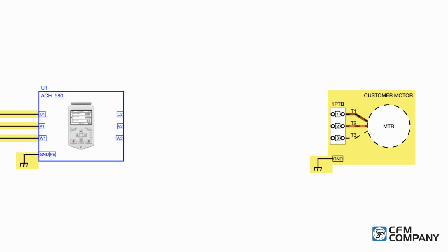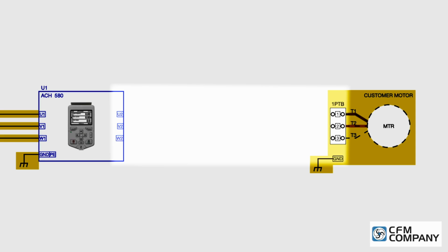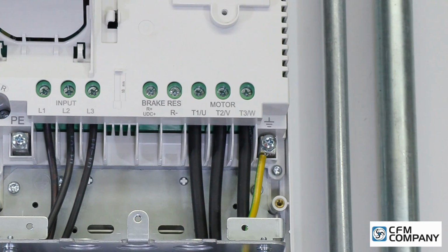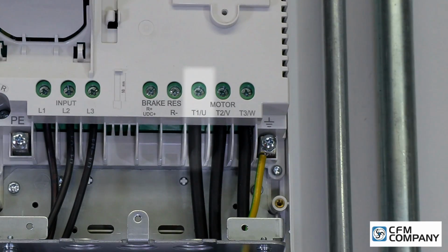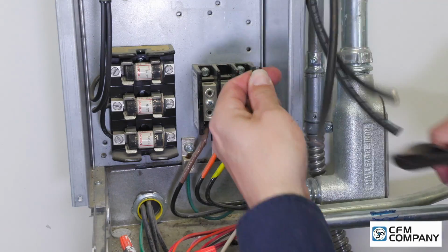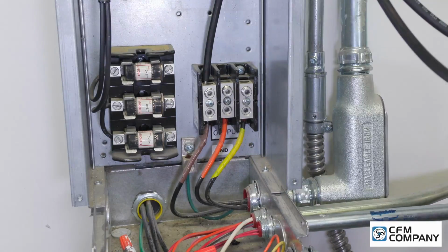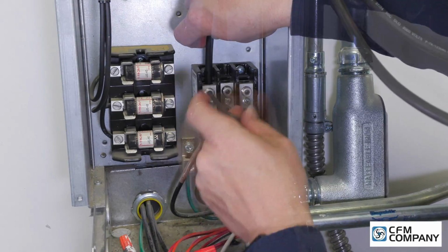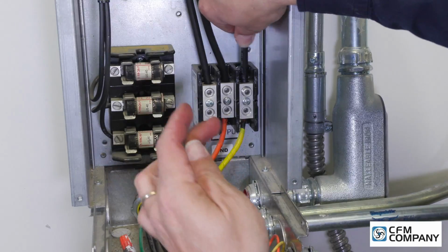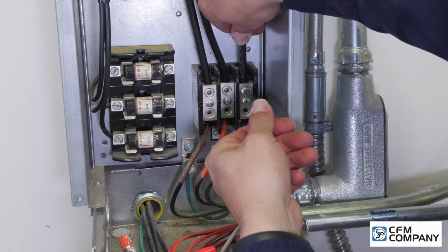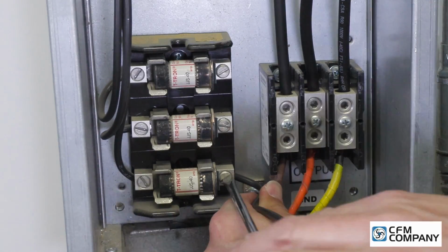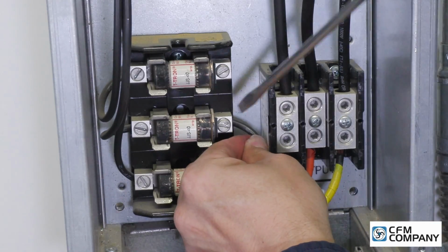The new conductors will need to reach between the drive output terminals and the motor terminal block. Land each new conductor on the drive motor terminals T1U, T2V, and T3W. Land the original ground conductor to the drive ground terminal. Cut the new output conductors to length at the motor terminal block. Land each output conductor to the line side of the motor terminal block. Next, install the 3 power wire conductors between the fuse block and the main disconnect.